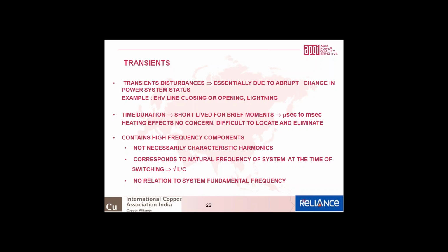Transients are basically very high frequency, maybe megahertz and kilohertz. It corresponds to the natural frequency of the system, that is 1 over root LC, where L is the inductance and C is the capacitance, and it has nothing to do with 50 hertz or 60 hertz, which is the power frequency. It is not a function of 2 times 50 hertz, 3 times 50 hertz, 4 times 50 hertz. It has to do only with the natural frequency of the system, which is in kilohertz or megahertz.